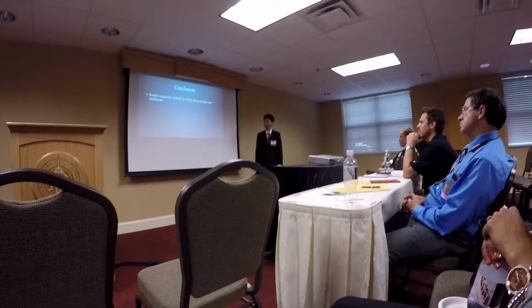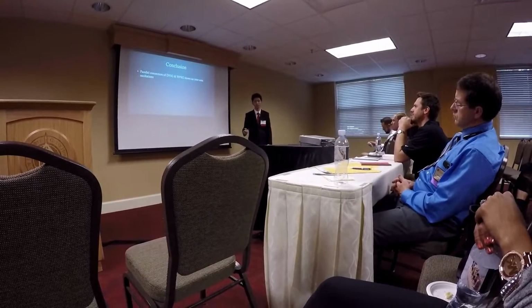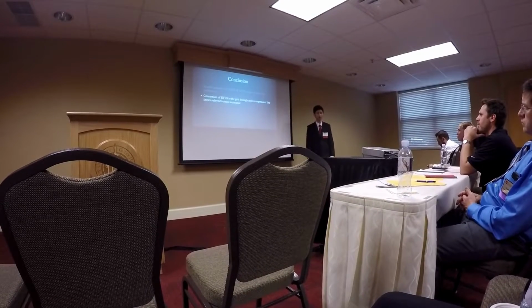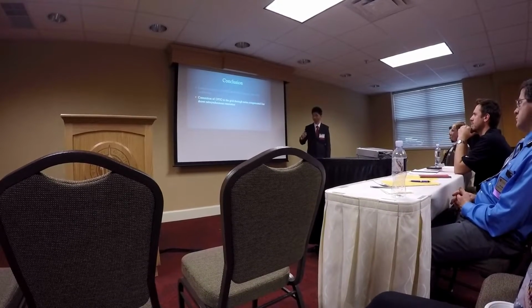And in that case, for the conclusion, for the first experiment with the parallel connection of the doubly fed induction generator with the one-field synchronous generator, I was not able to capture any inter-area oscillation. While for the connection of the doubly fed induction generator to the grid through a series compensated line, we were able to capture the subsynchronous resonance.